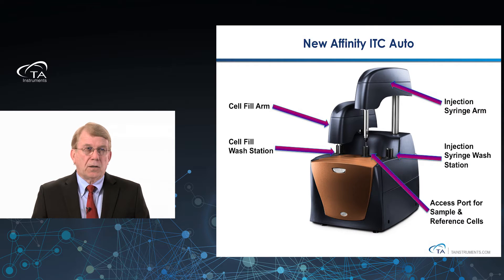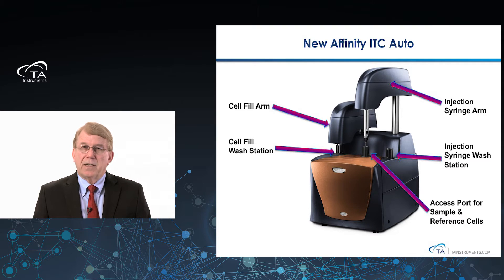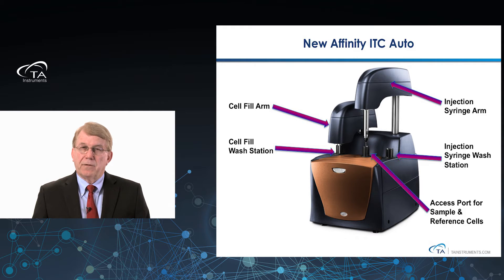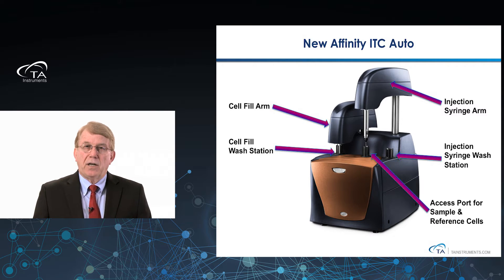The new Affinity ITC Auto goes even a step further by adding another automated arm on the left-hand side that fills the cell automatically when coupled to an autosampler. You have wash stations for both the injection syringe and the cell fill arm so that you can do fully automated cleaning. You have an injection syringe arm and then the access ports for the sample and reference cells. Think about a manual version that you can then fully upgrade in the field, with many new features.